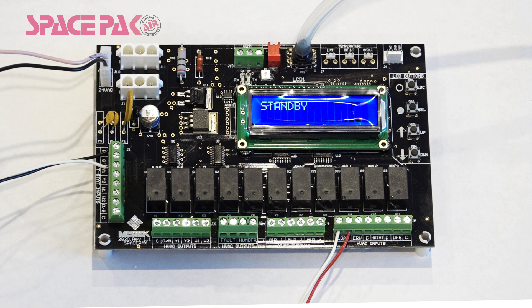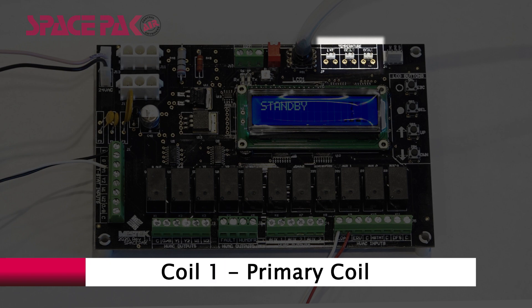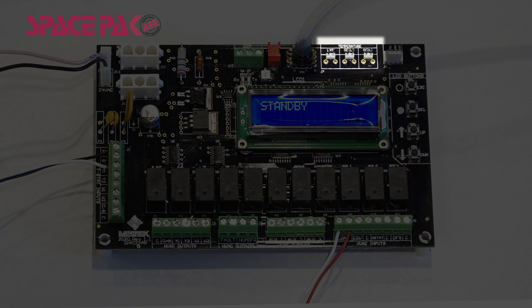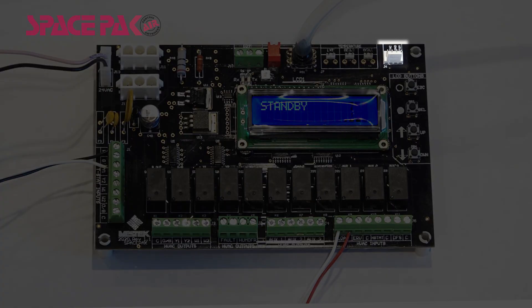The board also features three temperature inputs. The LAT input is for leaving air temperature, which is factory installed and displayed on the display screen. Coil 1 is dedicated to the primary coil located within the SpacePak air handler; the sensor is located on the coil itself and monitors and controls certain functions based on this temperature. Coil 2 temperature is optional and used for an external coil that can be field installed.